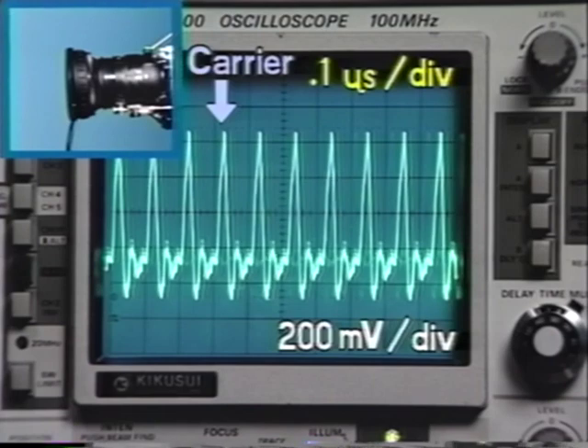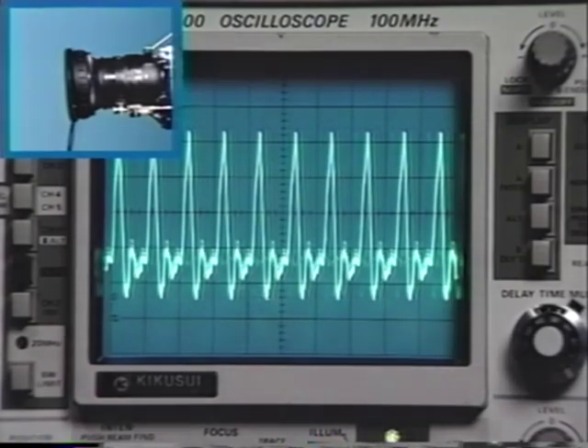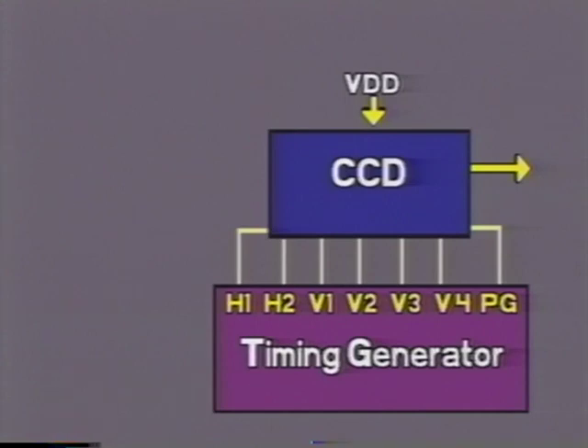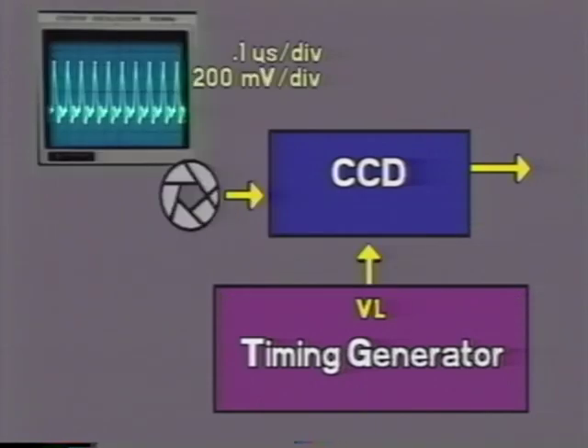The diminishing video signal not only proves that the CCD is producing a video signal, but that the iris is open. If no signal is present at all, check the VDD supply voltage, as well as the PG, H1 and H2 and V1 through V4 support signals output from the timing generator circuit to the CCD. If a carrier signal is present but no video signal is detected, then first verify that the iris is open and confirm the presence of the VL signal output from the timing generator before replacing the CCD imager.